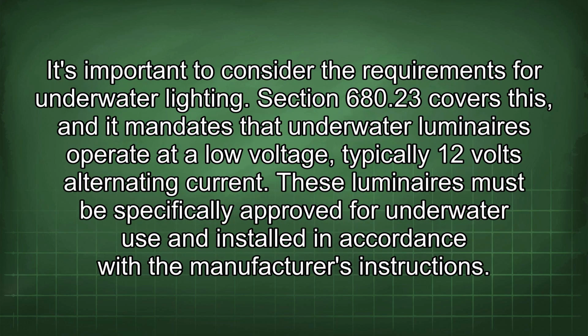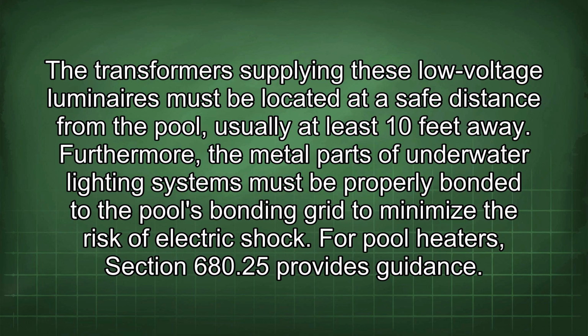It's important to consider the requirements for underwater lighting. Section 680.23 covers this, and it mandates that underwater luminaires operate at a low voltage, typically 12 volts alternating current. These luminaires must be specifically approved for underwater use and installed in accordance with the manufacturer's instructions. Transformers supplying these low-voltage luminaires must be located at a safe distance from the pool, usually at least 10 feet away. Furthermore, the metal parts of underwater lighting systems must be properly bonded to the pool's bonding grid to minimize the risk of electric shock.